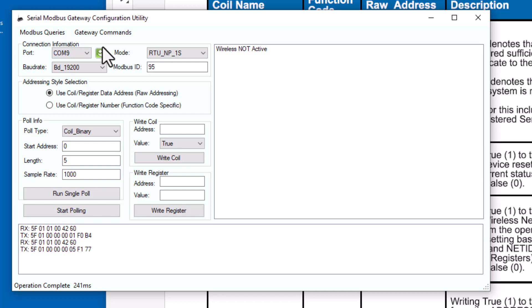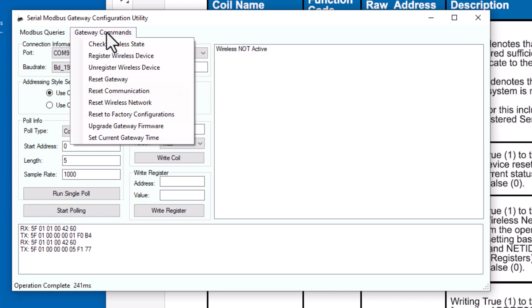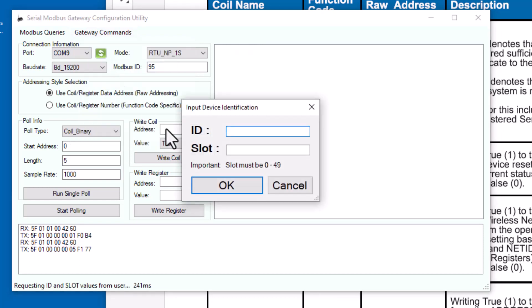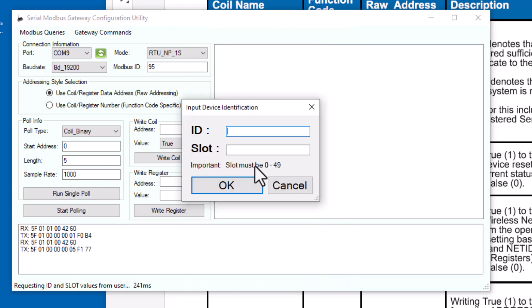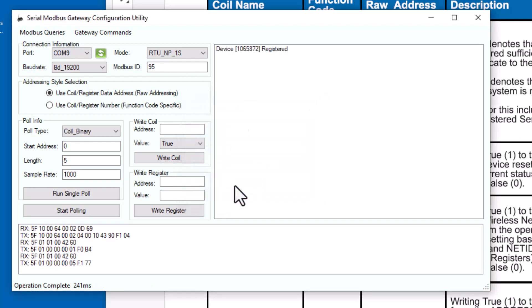There's three LEDs on the unit itself, and right now the bottom LED or the third is showing red, showing that the wireless is not active. We'll go Register Wireless Device. These Modbus gateways can accept up to 50 sensors, the first one being in slot zero. The first one I have is the long-range wireless temperature sensor. On the side of the casing there's a QR code label that also calls out the ID number. These are 900 megahertz sensors.